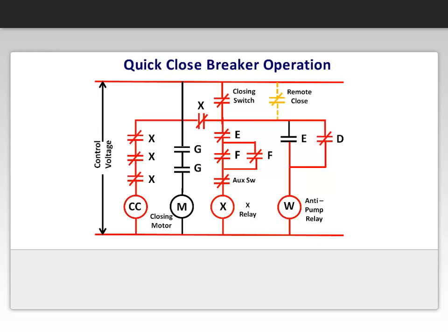The prop roller is released and the closing springs discharge and close the breaker, making the primary moving and stationary contacts meet. At the same time, the closing relay contact D closes to energize the anti-pump relay W. The E contacts reverse their state, providing an anti-pump feature, and the X relay de-energizes. The anti-pump relay feature allows one closure of the breaker for a single operation of the closing switch, no matter how long the switch may be held closed.